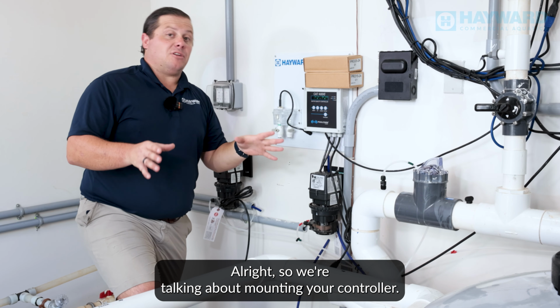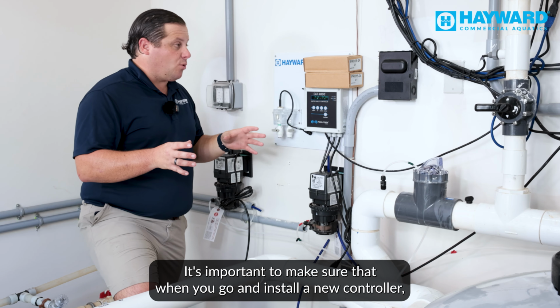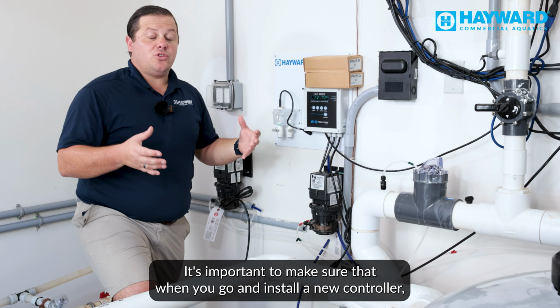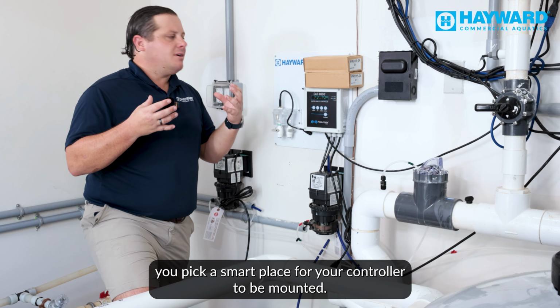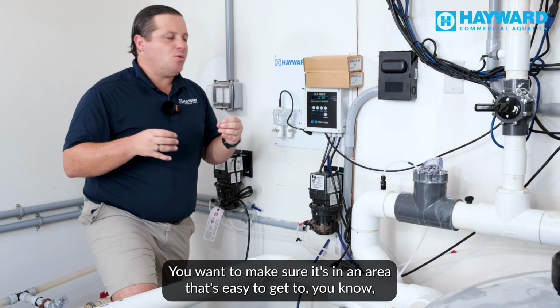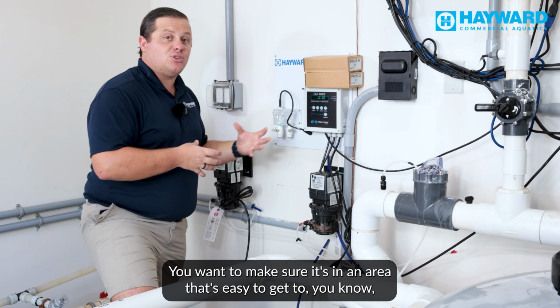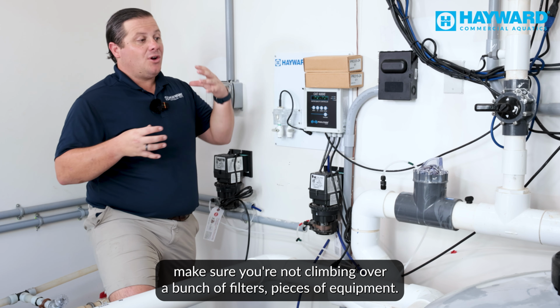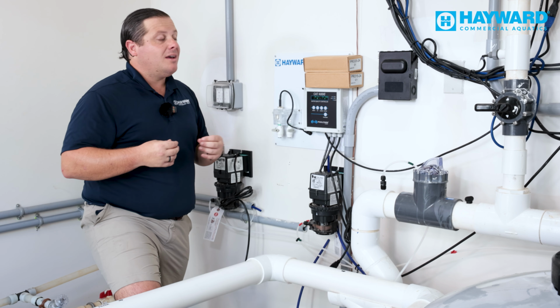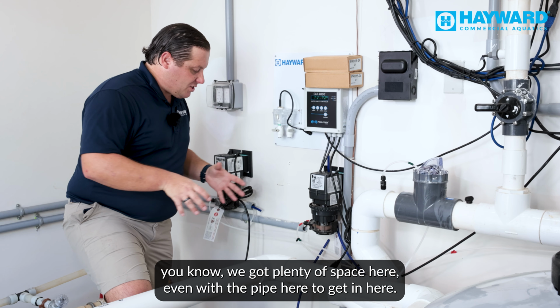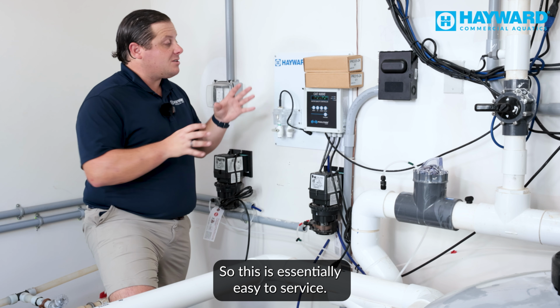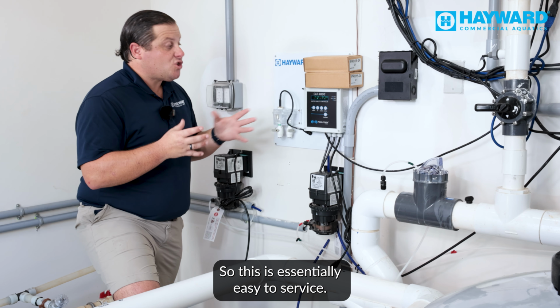All right, so we're talking about mounting your controller. It's important to make sure that when you go and install a new controller, you pick a smart place for your controller to be mounted. You want to make sure it's in an area that's easy to get to. You don't want to be climbing over a bunch of filters and pieces of equipment. You can see here, we've got plenty of space, even with the pipe here, to get in. So this is essentially easy to service.